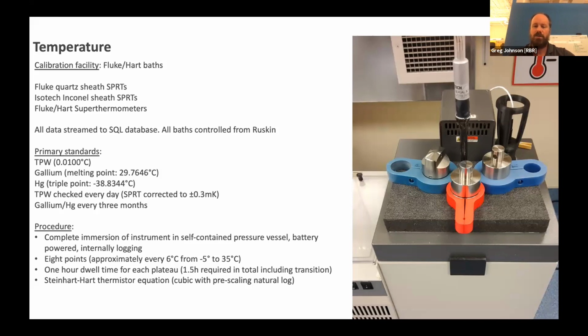All the data from these super thermometers goes into a SQL database. And then the instruments are typically deployed as these 3 are in the photograph, either fully submerged or mostly submerged, with all the measurement bits fully submerged down below. And we do about those 8 points, as I said, 6 degrees separation. And it takes us about 12 hours or so to do a cal. So the tanks are empty during the day because we're prepping for the next overnight run, and usually around 4 or 5 o'clock in the afternoon, they start to fill up with production's output. It takes about half an hour to do the transition of 6 degrees, and then we let them sit for an hour to be completely stable. And we take really just the last minute or so of data from each hour and a half in order to make sure that everything is as stable as possible.